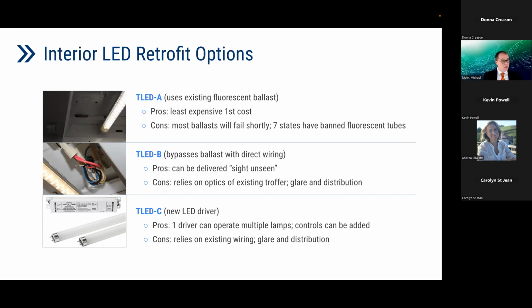So two takeaways: one, when you go to a type B or type C, label your fixture that it's been rewired and modified—there's a standardized sticker available for that. And two, keep your type A and type B fixtures away from each other, or don't relamp the same building with both types, just to prevent confusion and future problems.